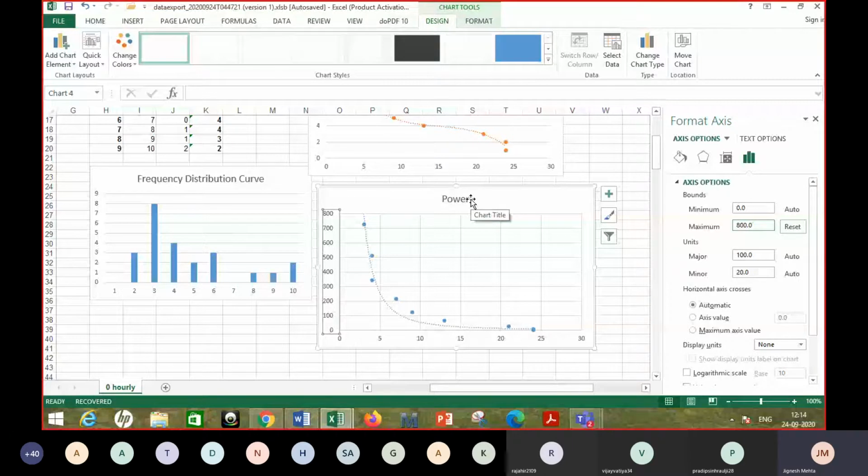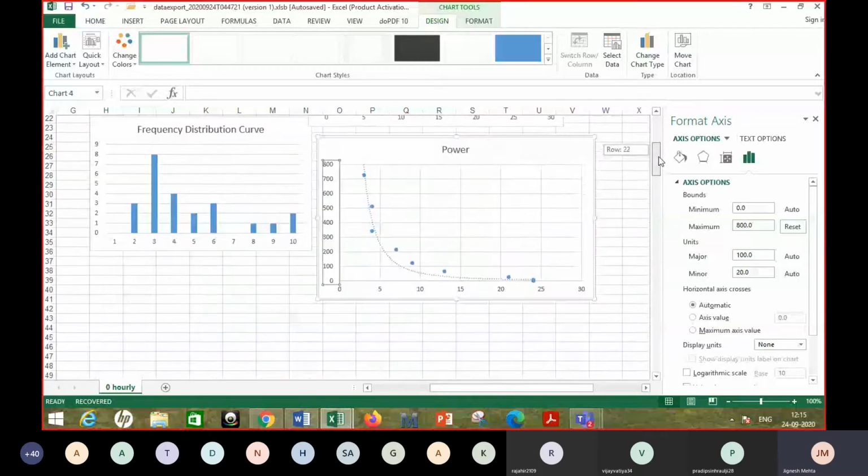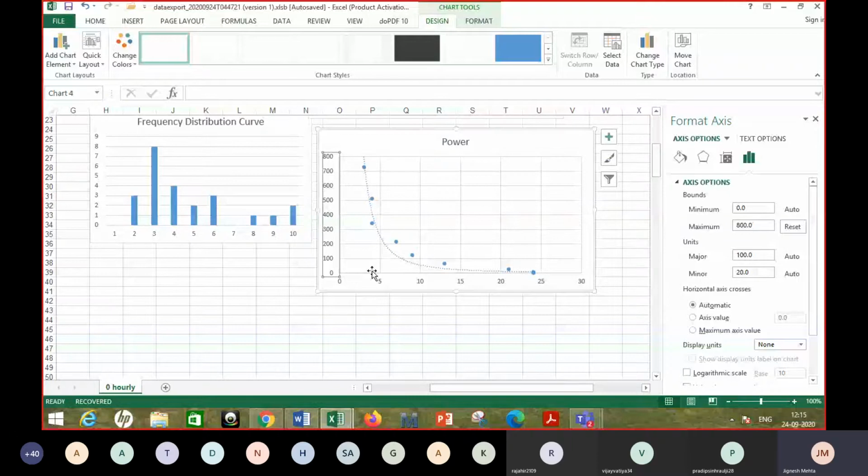And the power duration curve actually gives you an idea about how power will vary for a certain period, right? So you can see that for a certain period you get a very high amount of power from the wind, but for some other period you are going to get much lower power than that. Okay. Now at some points the velocity is very low, like here the velocity up to 3 may be so low that you are hardly producing any power, right?